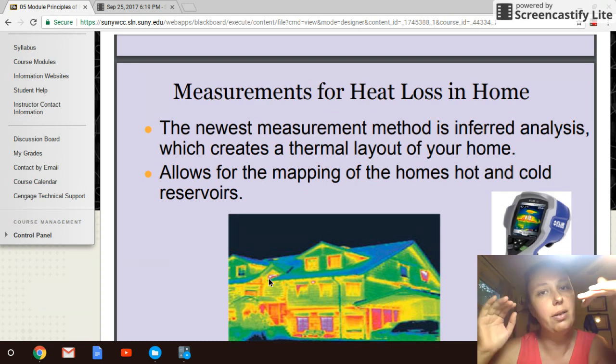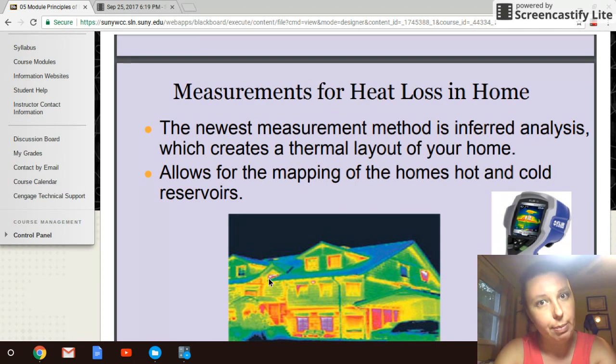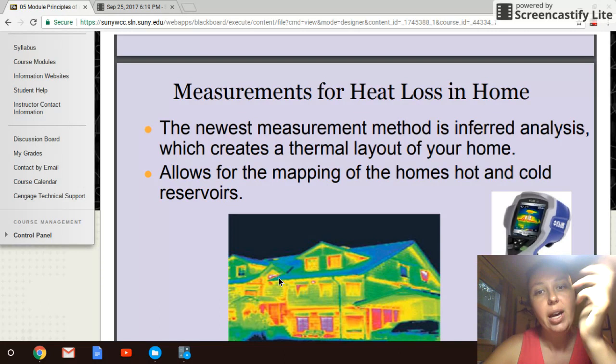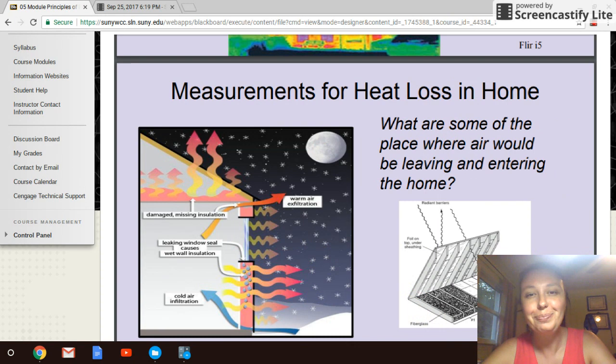Sometimes when you see a lot of exchange of heat energy, it's actually water damage within the building. When I would open up a wall inside, I would find a lot of water damage in that interface. So I would say there might be an issue with the siding material and the roof slope in that location, and it's something that I would look into when I see something like that. So it's something to think about, and this is our standard energy analysis. And once you get in the swing of working with this kind of imaging, you get really used to what you're seeing, and you can kind of call what you're looking at.